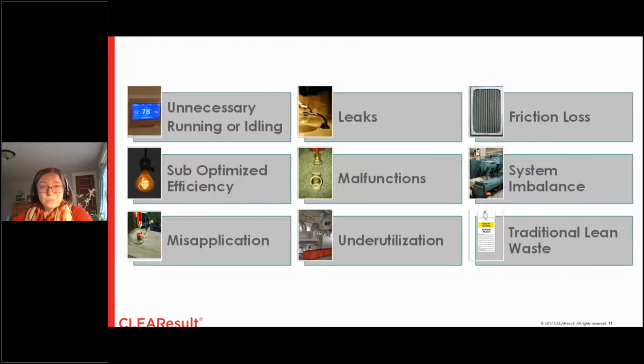By friction loss, we actually mean many different kinds of flow, including thermal energy. For example, if you've got a rooftop unit with an air-cooled condenser, and those cooling fins are caked with cottonwood fluff, dirt, and grime, there's a lot of resistance to that unit rejecting energy—so it runs too hot and uses extra energy. Friction loss can be a real boogeyman, but think about it broadly. Then there's suboptimized efficiency.